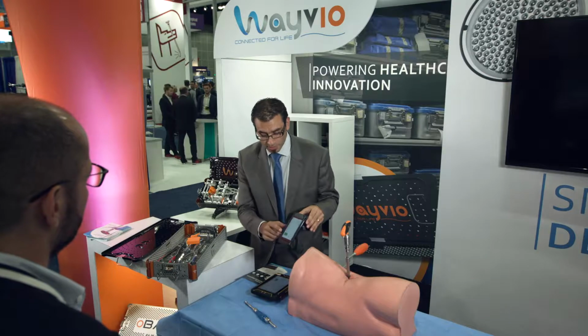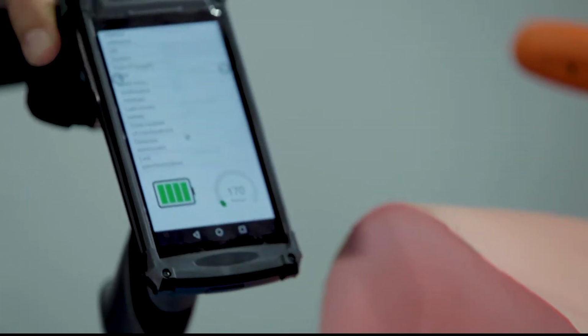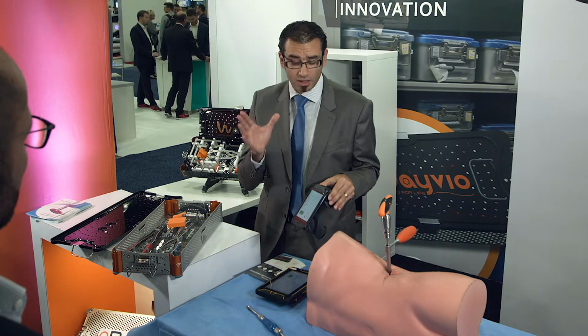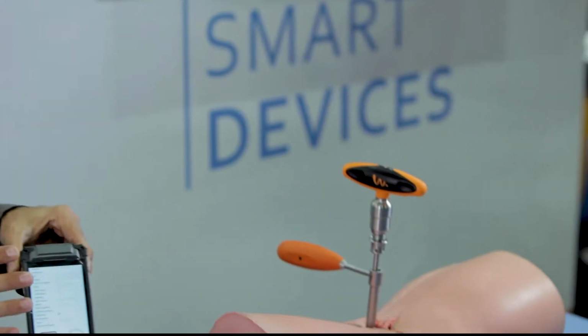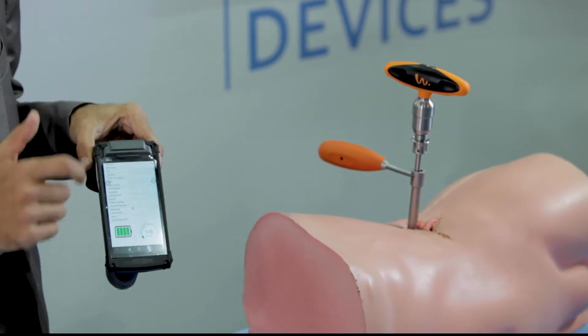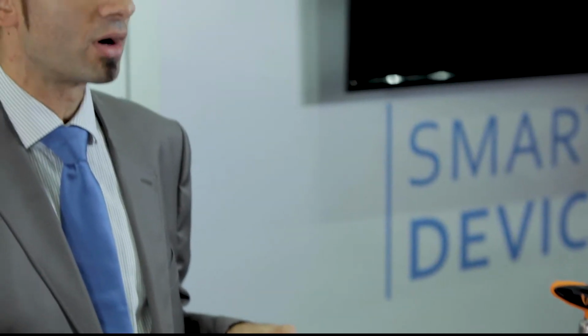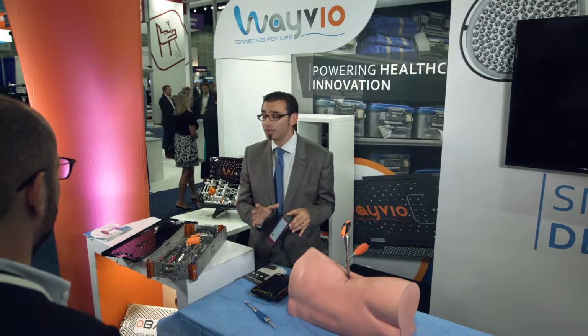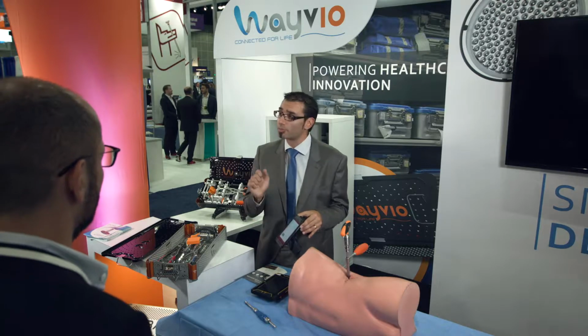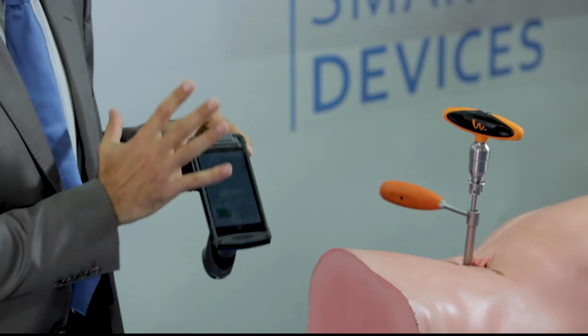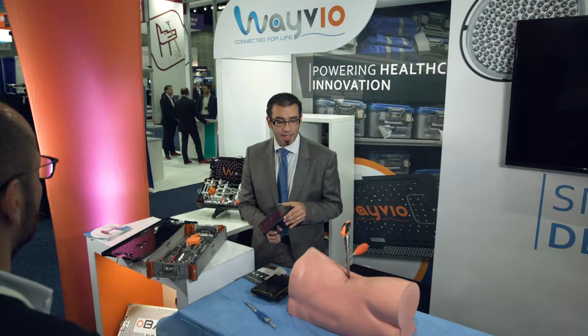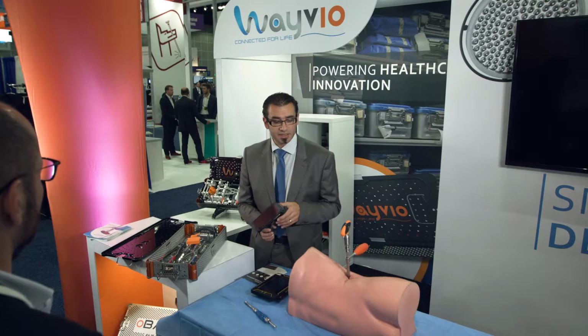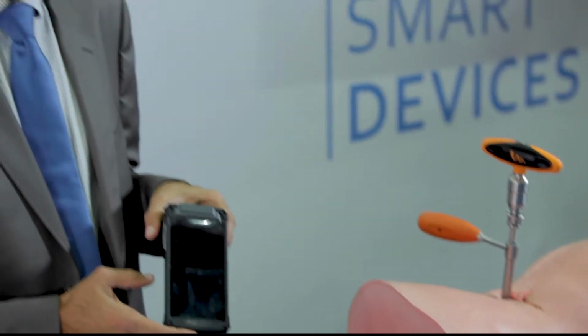And the battery? This little icon shows you the battery. The battery inside those smart instruments has been made to be autoclavable. All the electronics inside are fully integrated. The surgeon has no need to power on or power off the instruments. The battery has no need to be recharged. So we needed a battery that is fully autoclavable. All the electronics inside are fully autoclavable, and the whole instrument has been validated, so it will last at least 500 sterilizations and 6,000 releases for the torque limiter.